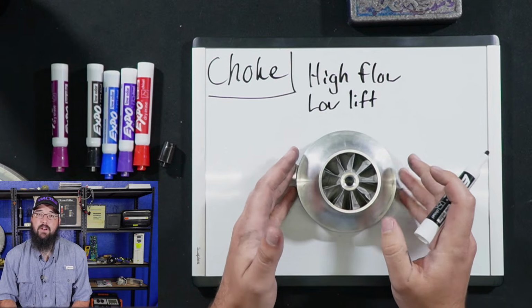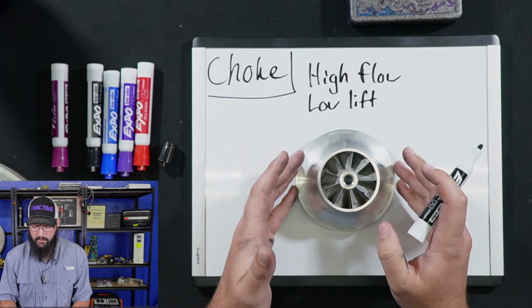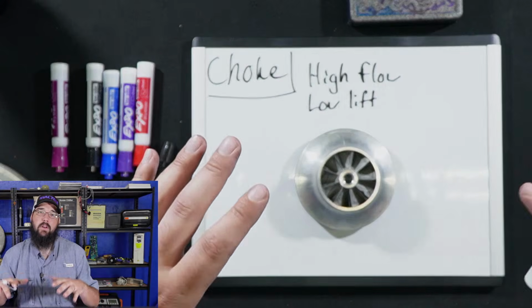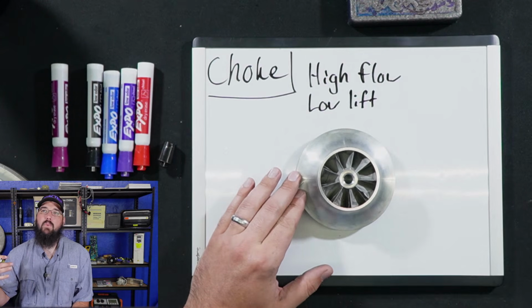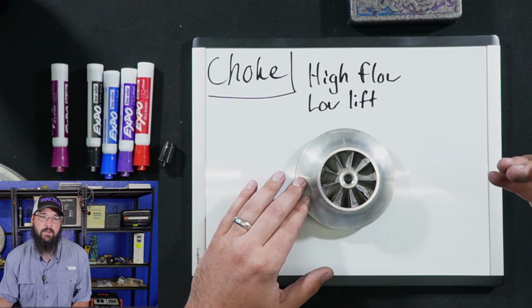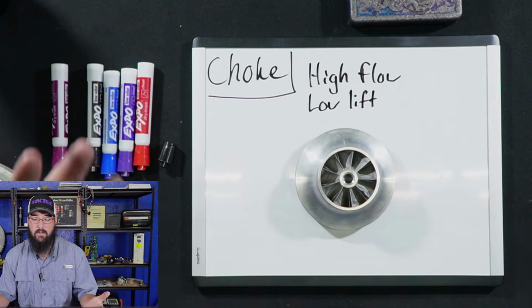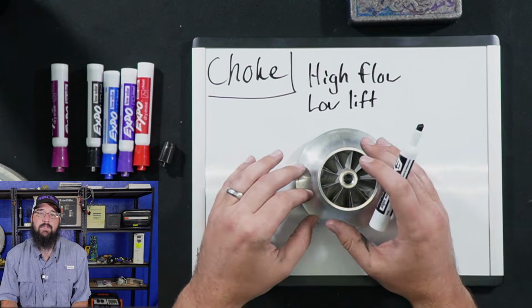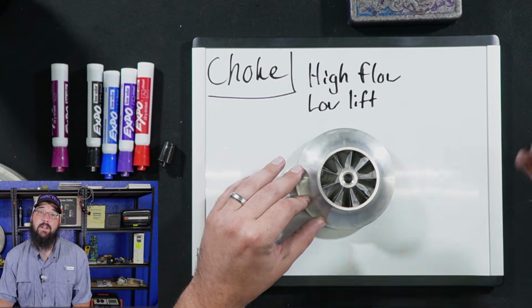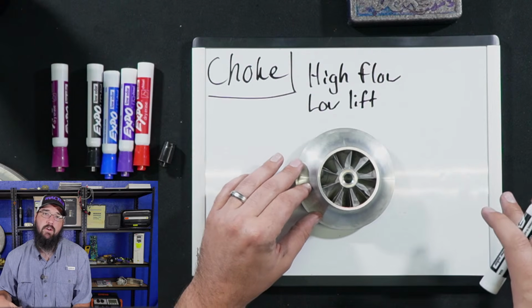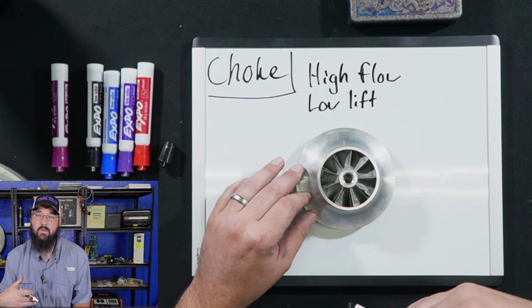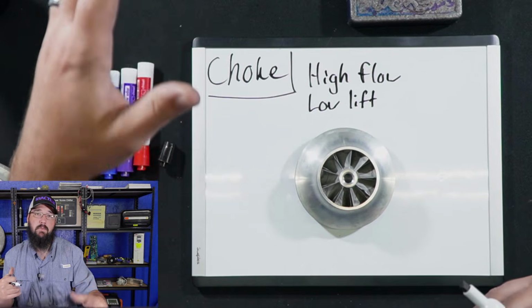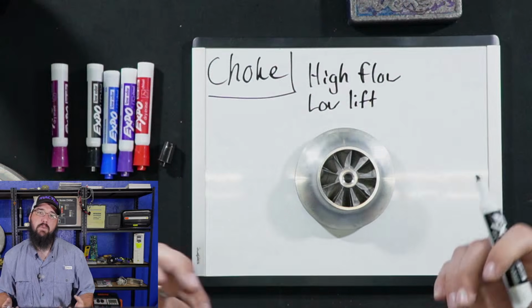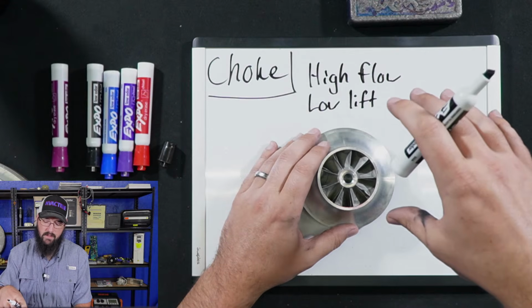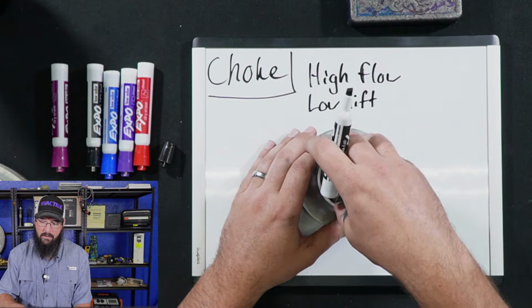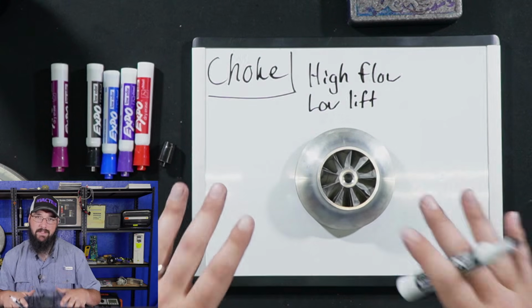Choke is something we have to be careful of when we're doing condenser relief, when we're trying to unload the condenser and run a really low condenser water temperature while also having a high load on the evaporator, in a lot of process applications or large facilities, data centers, things like that. This is a scenario where you're likely to run into this. We have a low ambient outside. We can get our condenser water down, or we're pulling from a geothermal source of some kind, whether it be a lake or a body of river water or something like that. So we're able to pull from a geothermal source and get condenser relief. We're able to get the condenser water down.